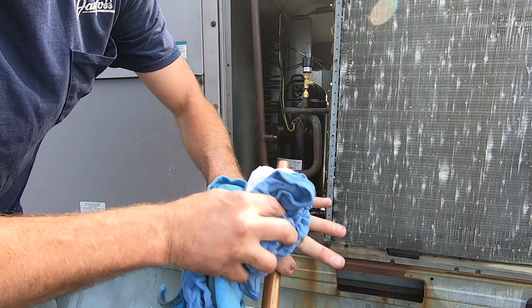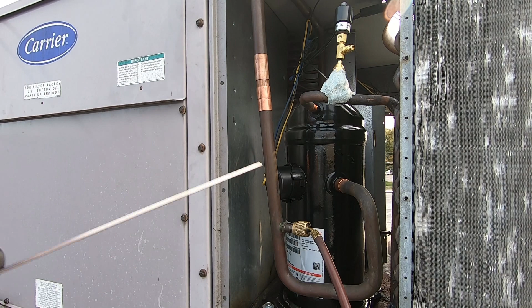All right, everybody, I got the pipe fitted in. Got a little wet rag here around this pressure switch. I've got my nitrogen flowing. I'm gonna go ahead and braze in the compressor, and then we'll hop inside and braze in the filter dryer.